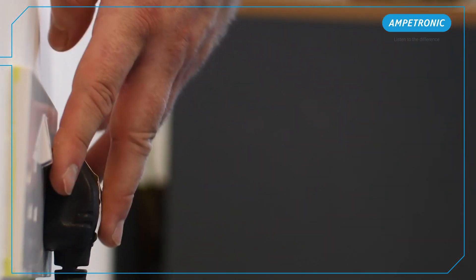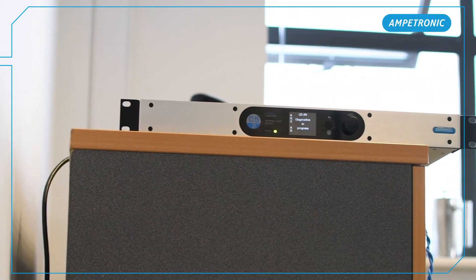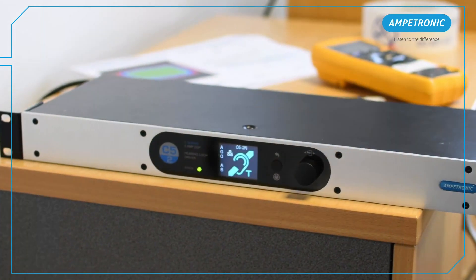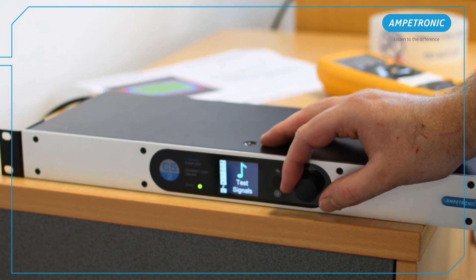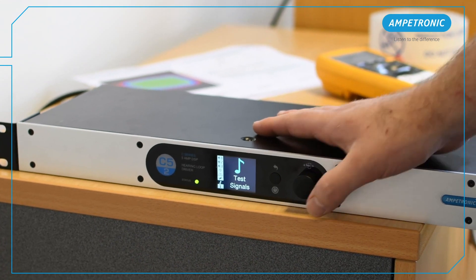On site, it could then be a long wait until the amplifier is connected and powered up, but if possible, it's a good idea to carry out a quick test. Assuming your previous cable tests were okay, the amplifier should start and pass all of its self-diagnostics. This is the first opportunity to ensure the actual cable path was followed accurately and check the performance of the system.